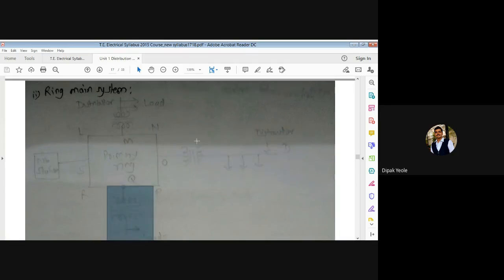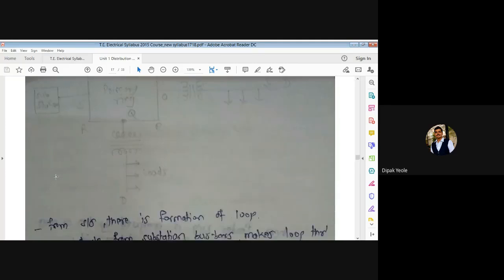तुम्हाला कळत असेल की आता इथे ट्रान्सफॉर्मरचा सिम्बॉल काढलाय सरांनी, म्हणजे ही कोणती सिस्टीम आहे? एसी रिंग मेन सिस्टीम. Yes, and what is the application of ring? If there is a fault on one particular feeder, then you can transmit or transfer the power from the other end, either from this end or from this end. Yes, so this is the application or advantage of the ring main system.